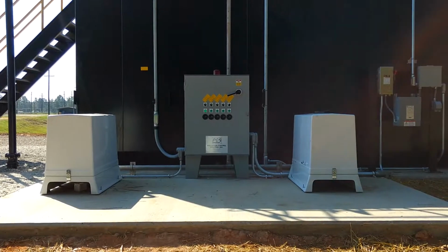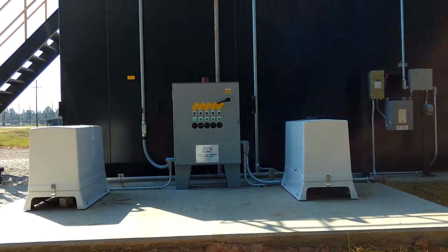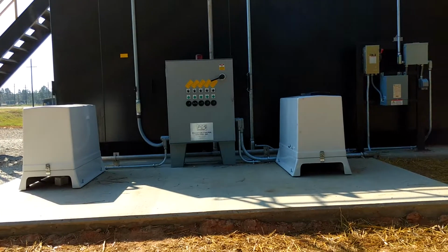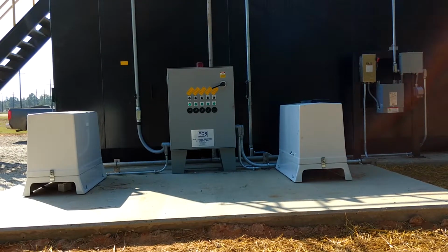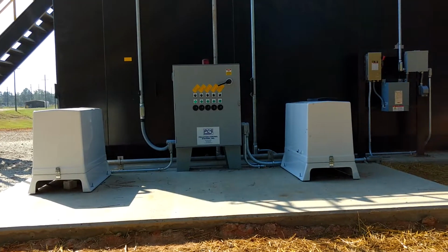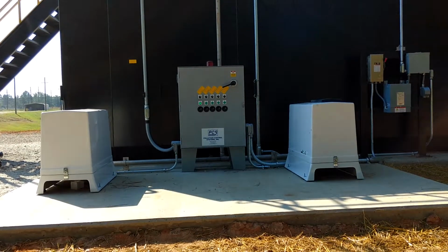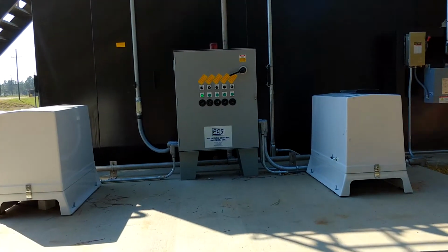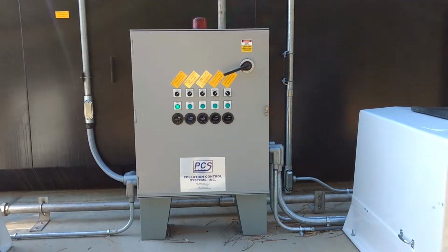The control panel and 2 blowers for the packaged wastewater plant. The blowers provide compressed air and diffused dissolved oxygen into the aeration chamber for the bacteria that are doing all of the work. The control panel is used to control the blowers, sludge pump to empty the sludge holding tank, and also the equalization pump.